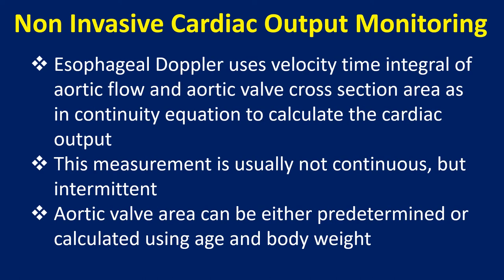Esophageal Doppler uses the velocity time integral of aortic flow and aortic valve cross-section area, as in the continuity equation, to calculate cardiac output. This measurement is usually not continuous but intermittent, and aortic valve area can be either predetermined or calculated using age and body weight.